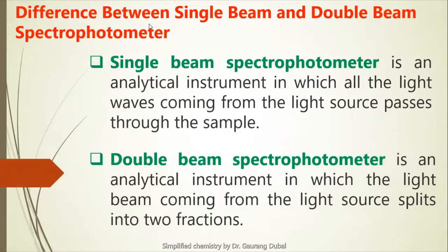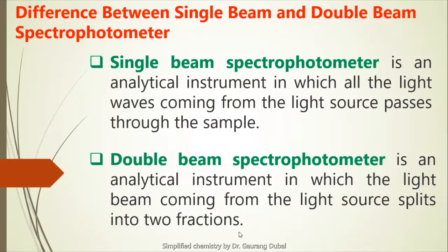Now we are going to see the differences between single beam and double beam spectrophotometer one by one. The first difference: in a single beam spectrophotometer, all the light waves coming from the light source directly pass through the sample, while in a double beam spectrophotometer, the light beam coming from the light source is split into two fractions.